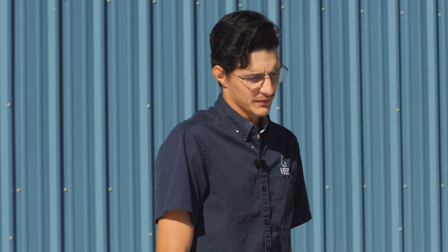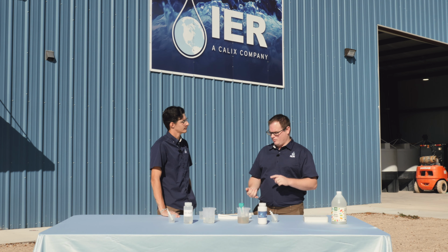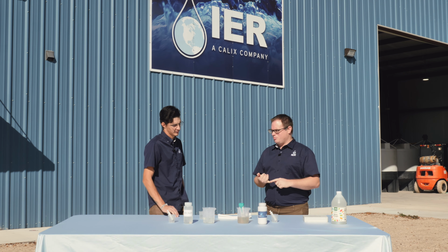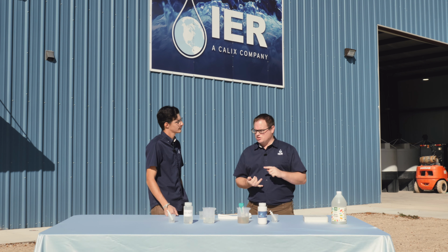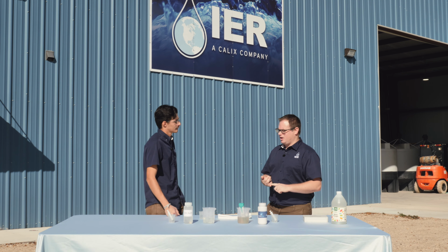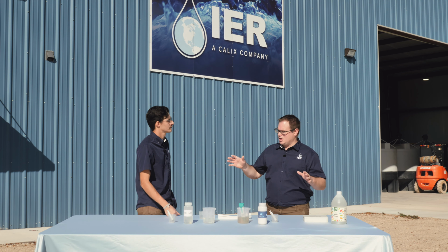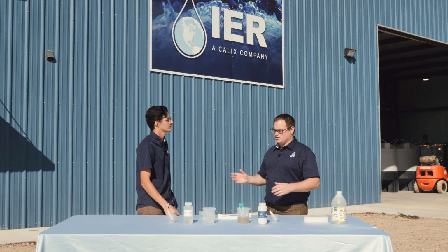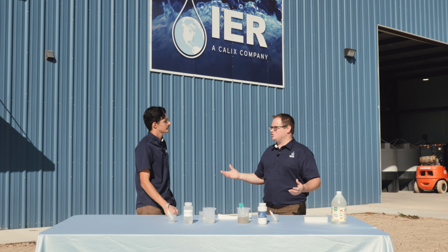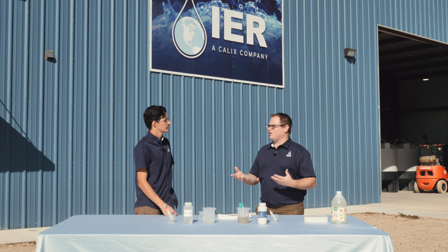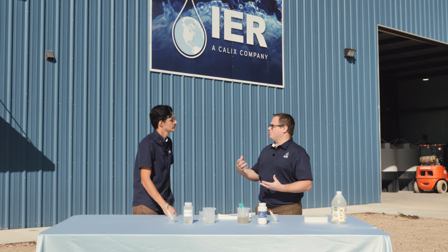All right, John, so one more question. What exactly, or why exactly, will we use this for wastewater treatment plants? So at a wastewater treatment plant, of course, the first thing they want to look at is using it to adjust pH. But it goes beyond that. They're also looking for an alkalinity boost in a treatment plant. Caustic soda will raise your pH. It just raises its pH, but because it wants to release that hydroxide instantly, it allows no buffer in the system. And alkalinity, really, you could say alkalinity is kind of what's your buffering capacity of your water.